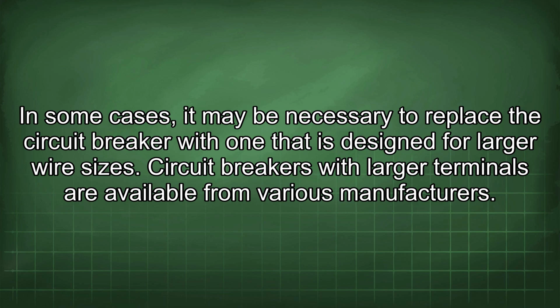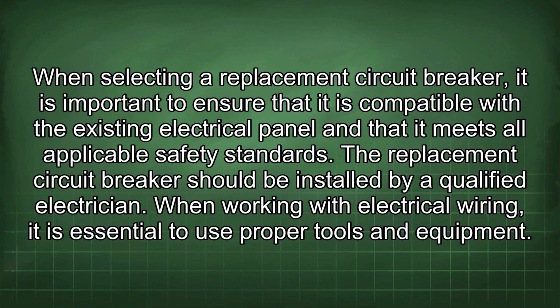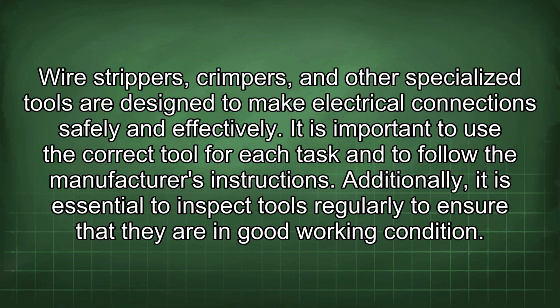In some cases, it may be necessary to replace the circuit breaker with one that is designed for larger wire sizes. Circuit breakers with larger terminals are available from various manufacturers. When selecting a replacement circuit breaker, it is important to ensure that it is compatible with the existing electrical panel and that it meets all applicable safety standards. The replacement circuit breaker should be installed by a qualified electrician. When working with electrical wiring, it is essential to use proper tools and equipment. Wire strippers, crimpers, and other specialized tools are designed to make electrical connections safely and effectively.